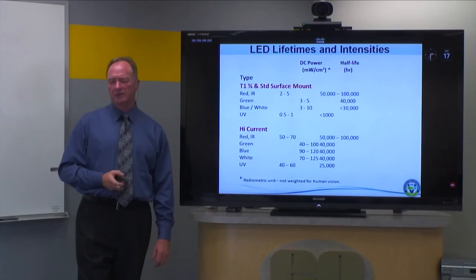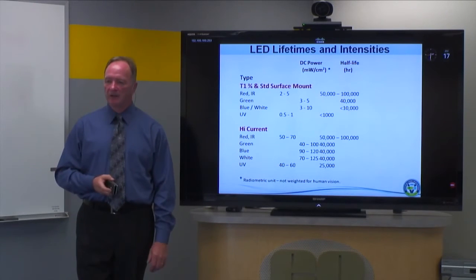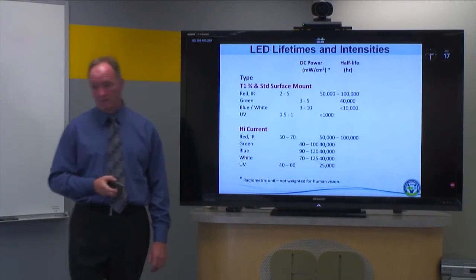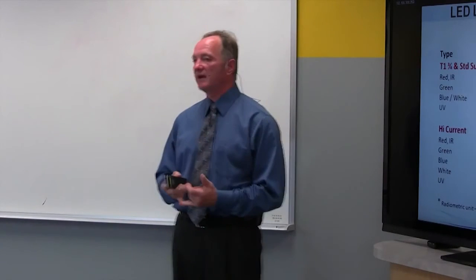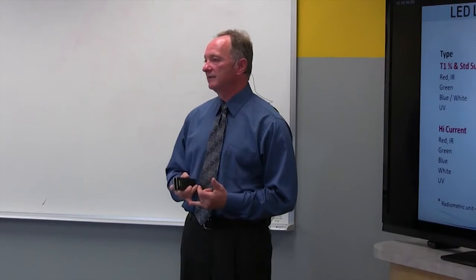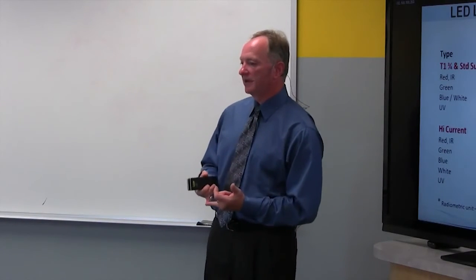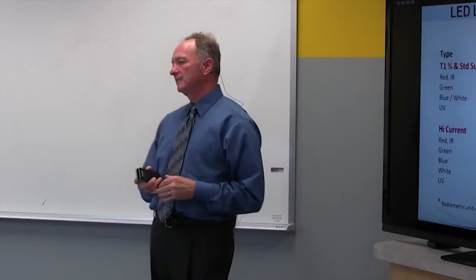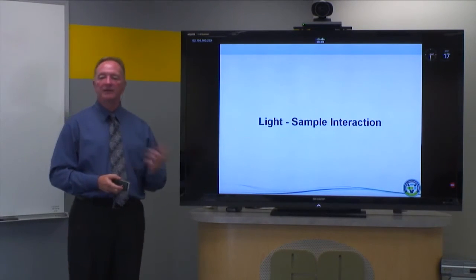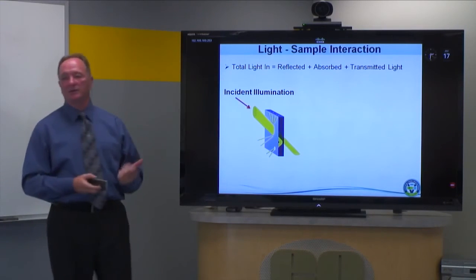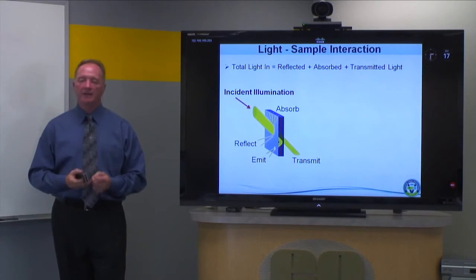On LED lifetimes: high current LEDs tend to have a lot of radiant power and tend to last longer. Even UV LEDs, which were normally very short-lived, now last much longer — up to 25,000 or 30,000 hours on time. That's considered a half-life: after one half-life you have 50% of your intensity left, and after another half-life you have 50% of that, so it's an exponential function.